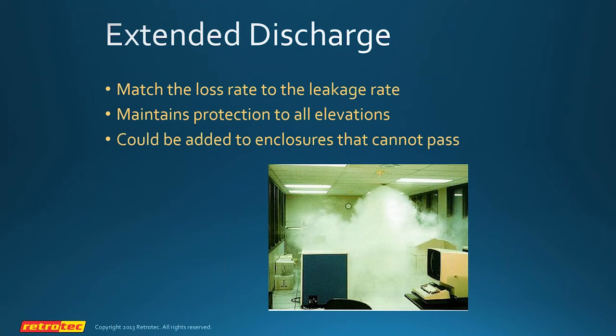What the extended discharge does is to discover the loss rate in the enclosure and to simply require that you have an extended discharge at the same flow rate as the loss rate, so that you are essentially replacing the agent at the top of the enclosure at the same rate as it's flowing out the bottom.